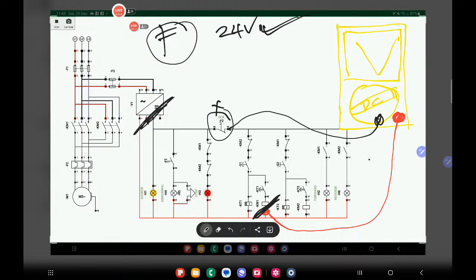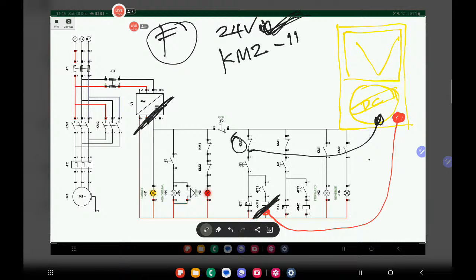So after this, I'll move the probe to terminal 11 of the KM2, and for sure I'll have 24 volts. And then I'll move my probe to number 12 of KM2 again. Then I should be having 24 volts. If I don't have 24 volts, then my KM2 terminals 11 and 12 are causing the trouble for our system, because this would be the reason why we don't have forward operation.